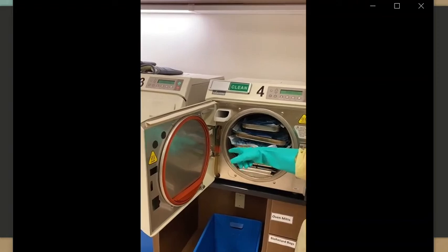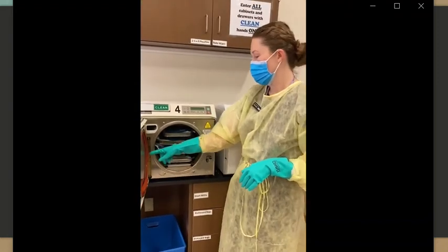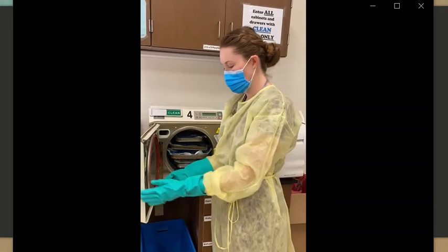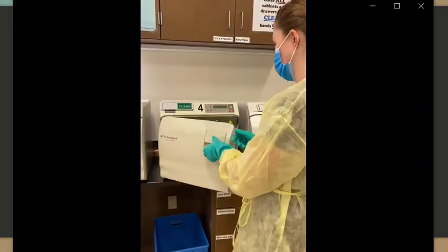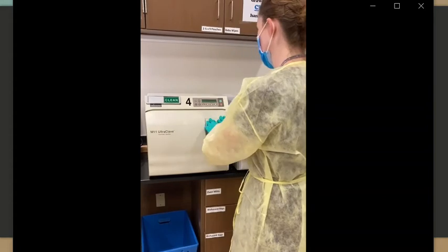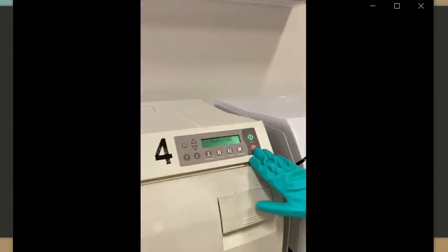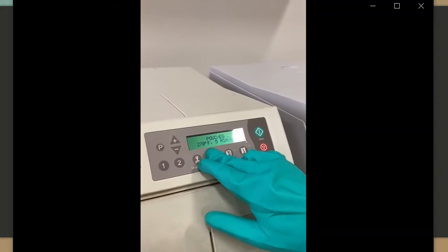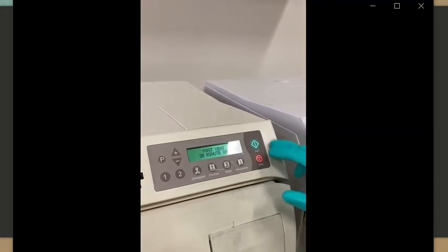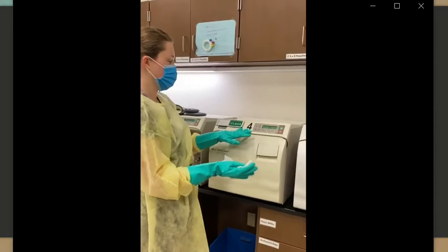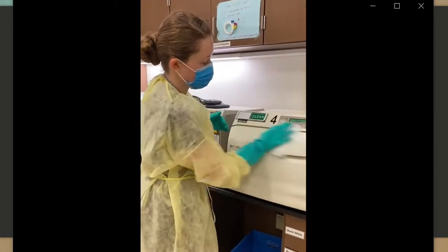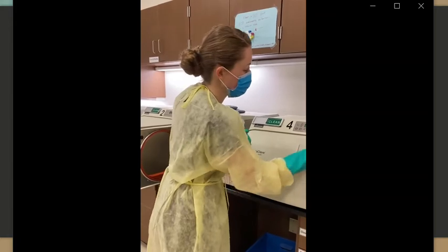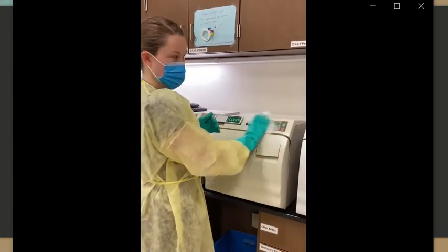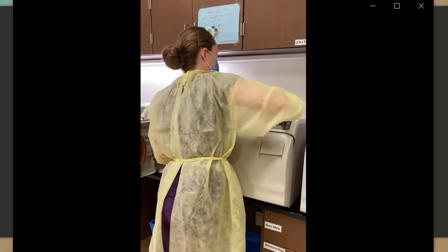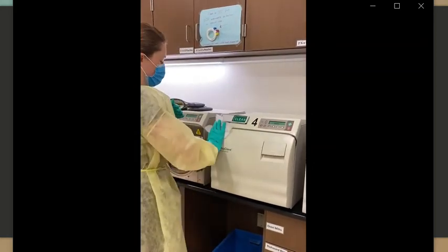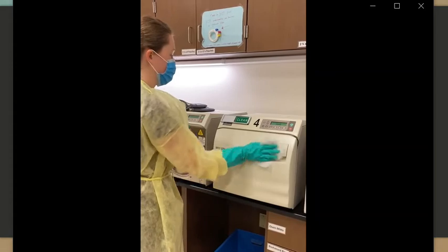Next, you can see that I am checking the water level. You can see the red and the green, and we're making sure that the distilled water is filled into the green. Next, I'm going to check the gasket, making sure that it is flush. And we're going to shut the autoclave. And out of our options, since we're in pouches, we hit pouches and start. After starting the unit, you want to make sure that you grab disinfecting wipes and you wipe the outside of the unit. Not just the handle, make sure that you're wiping the entire thing because we're all wearing dirty gloves when we load them and you're not sure exactly what was touched. So just wipe the entire thing down thoroughly.